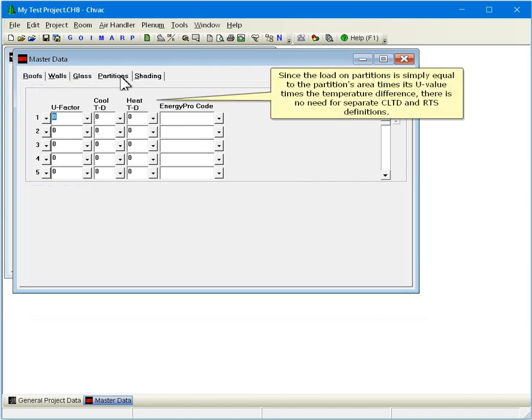Now click the Partitions tab. Since the load on partitions is simply equal to the partition's area times its U-value times the temperature difference, there is no need for separate CLTD and RTS definitions.